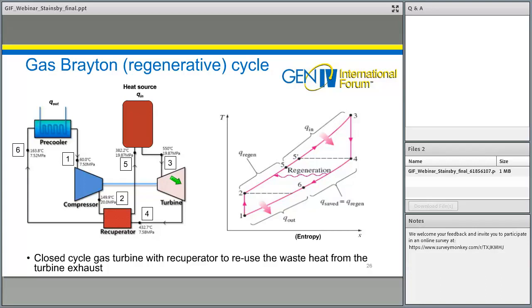So this is a recuperated gas turbine which works in a closed cycle. We put in heat from a heat source, which could be directly from a reactor core with a gas reactor, or via a heat exchanger coupled to a liquid metal reactor, for example. The heat goes into the fluid, typically helium, could be nitrogen, and that fluid drives the turbine. The gas expands down through the turbine, losing pressure and temperature, but it's still quite hot.